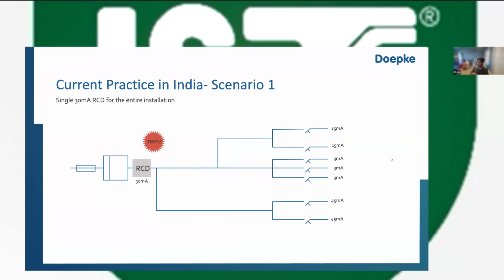So you're fine. But in India, unfortunately, we see something very different. Oftentimes, though this is again not very true for the elevator industry, we have one 100 milliampere RCD installed for the entire installation, and then this will trip. Or one 500 milliampere RCD, but on the circuits that require 30 milliampere, like for example sockets or lighting, then you have a shock risk. So these are the problems that can occur.